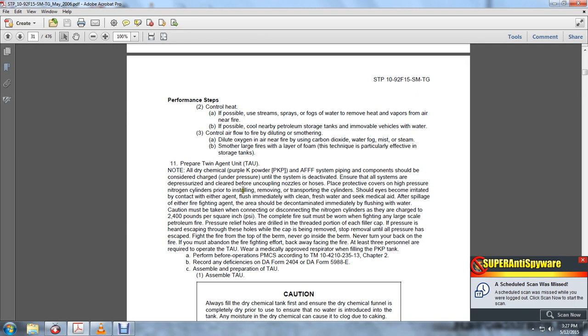Should the eyes become irritated by contact with the agent, flush immediately with clean fresh water and seek medical aid. After a spillage, and after each use, the firefighting agent areas should be decontaminated immediately by flushing with water. Caution must be taken in connecting and disconnecting nitrogen cylinders, as they are charged to 2,400 pounds per square inch. A complete fire suit must be worn by firefighters on large scale petroleum fires.